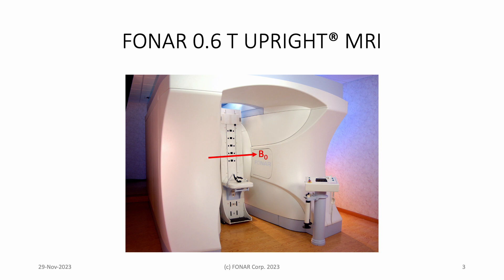that can be rotated through 360 degrees about the B0 axis. The field orientation and open architecture of the magnet enables static and dynamic imaging in a wide variety of patient postures, such as sitting, standing, and lying down, and in every orientation — prone, supine, and decubitus.